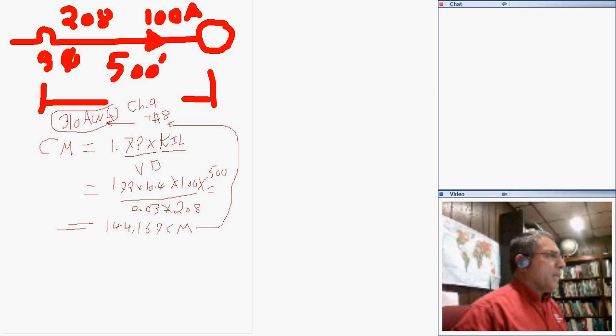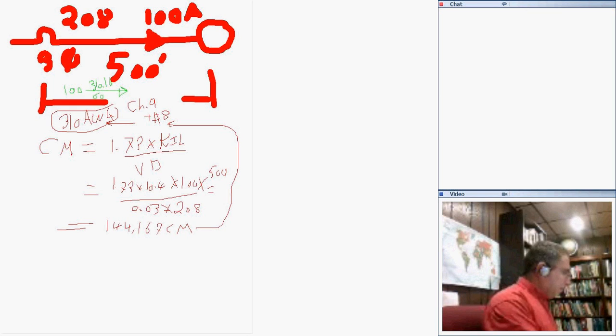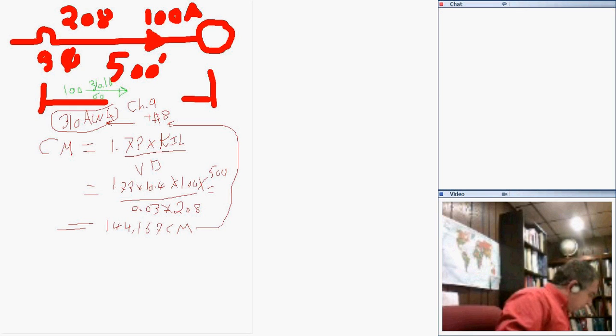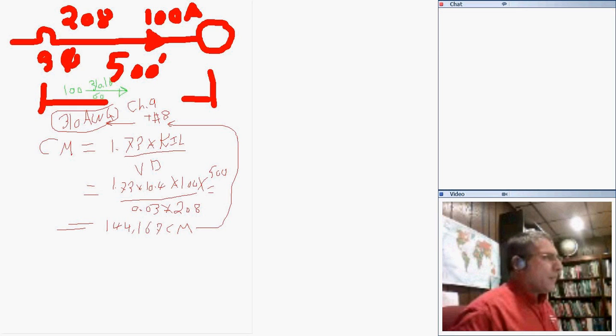just as 100 amp non-continuous, you size it just based on 100 amp, and you take this one to 310.16, and set 100 amps, you go to the 60 degree column. If you go to this one, what would that be? Number 1. If you go to this, that will get you number 1. So emphasize, guys, based on the voltage drop calculation, you came up with 3 aught.